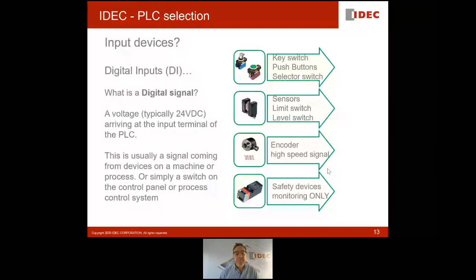This signal is usually coming from a device on the machine or a simple switch on the control panel or somewhere on the process. This could be from a push button or a key switch or a selector switch. It could be from a sensor, which is detecting the presence of a part that's about to be worked on, or a carton on a production line. It could be from a limit switch on a door or a gate. It could be a high-speed input coming from a rotary encoder, determining speed or position. Or it could be a signal coming from a safety device. Of course, the monitoring contacts only, because the safety signals will be going through a different set of hardware. So this is our digital input. Simple 1 or 0.